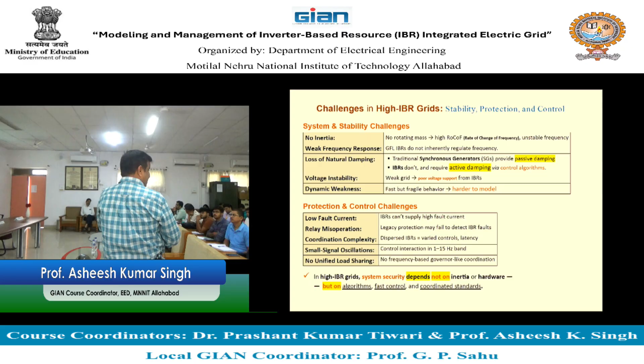IBRs don't, and they require active damping through control algorithms. Clear? It is possible to have, but for that we have to employ control techniques or active damping methods. Voltage instability means weak grid, that goes to poor voltage support from IBRs. Dynamic weakness, that is fast but fragile behavior, and the problem is it is difficult to model. When modeling is difficult, then definitely finding solutions is also difficult.